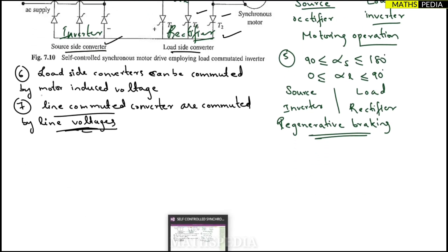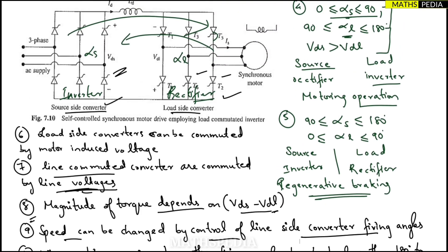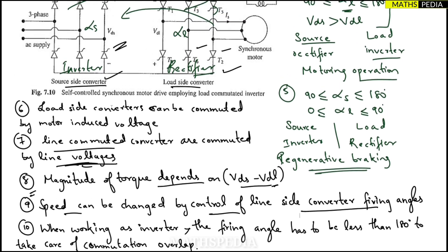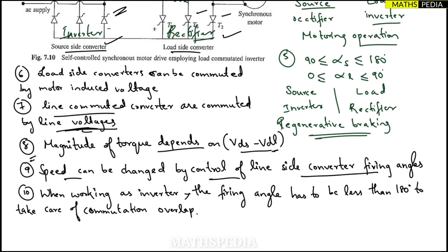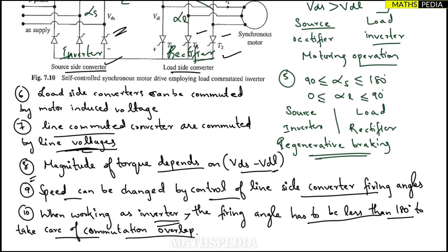The magnitude of torque depends on Vds minus Vdl. Speed can be changed by controlling the line side converter firing angles — that is, by changing the firing angles of the source side converter thyristors. When working as an inverter, the firing angle must be less than 180 degrees to take care of commutation overlap, so the thyristors don't get overlapped. This applies to both the source side and load side converters.